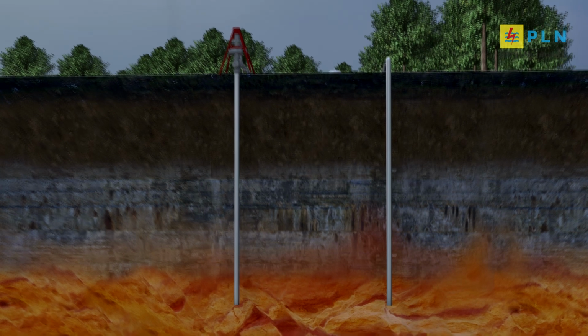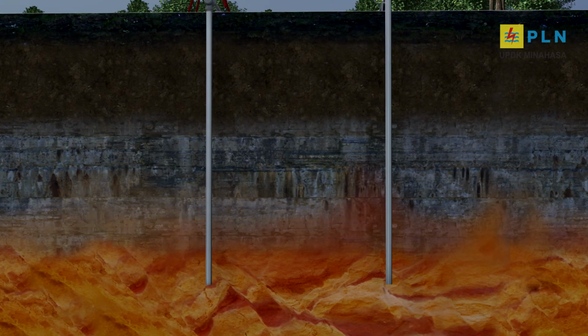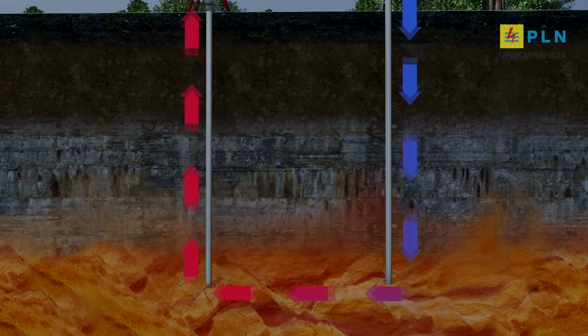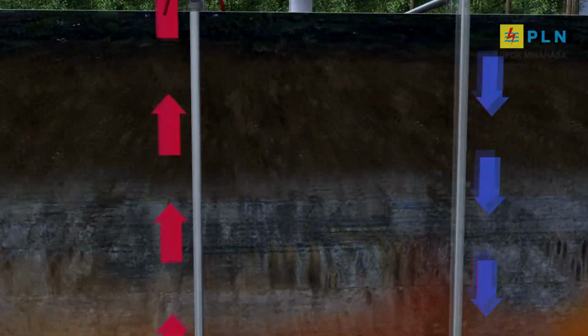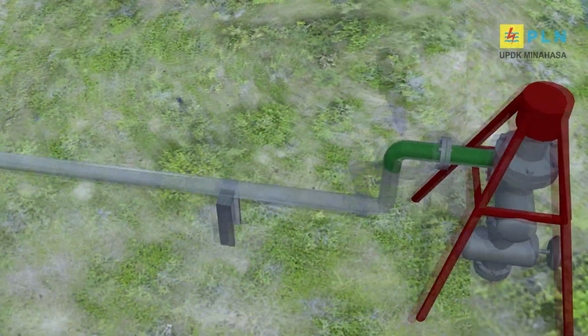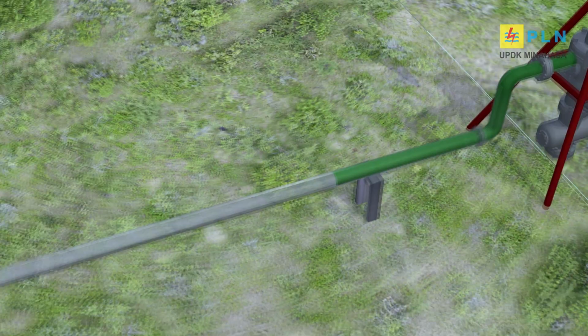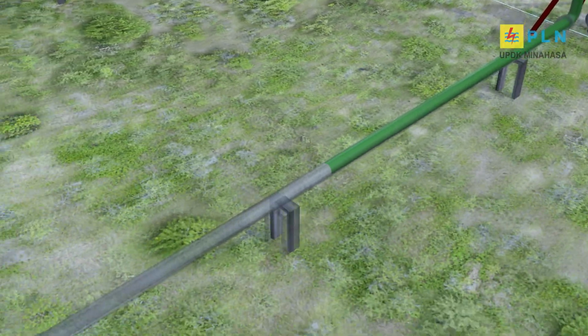Overflow water from the cooling tower basin enters the re-injection basin, which is then pumped into the PGE injection well to be re-injected into the Earth reservoir to be heated before being reused. That is what makes geothermal energy a renewable energy.